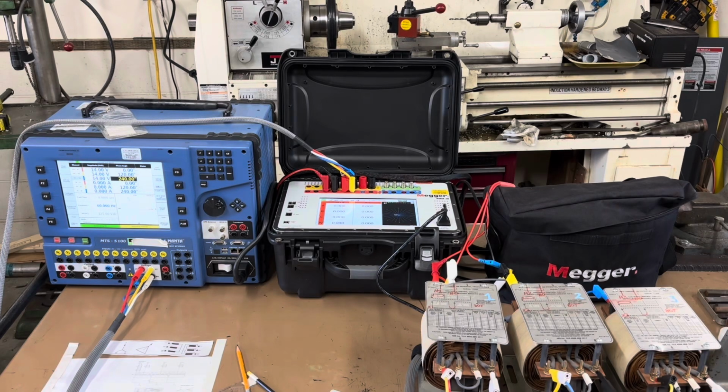This is going to be a practical demonstration of transformer vector groups and what happens when you reverse phase sequence or rotation to a transformer. On the bench here, we've got a Manta 5100 that we're going to be using as a voltage source.